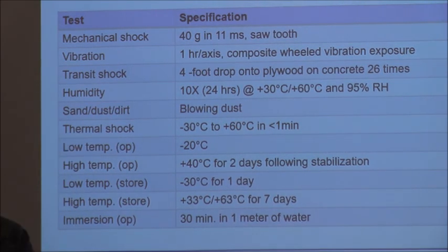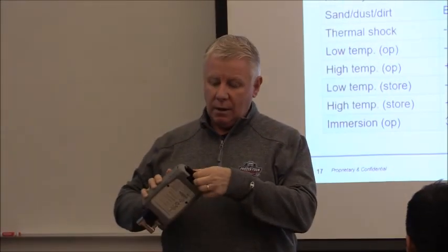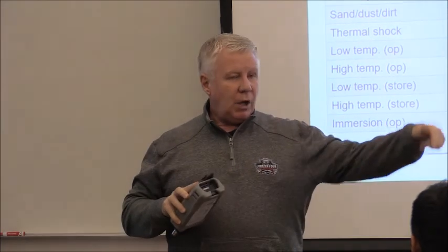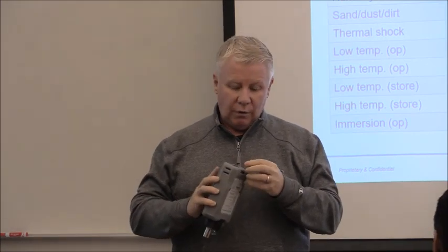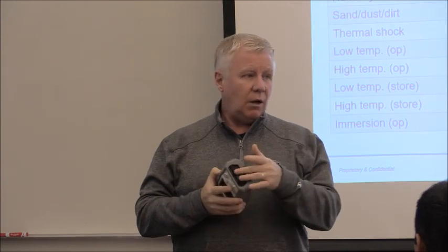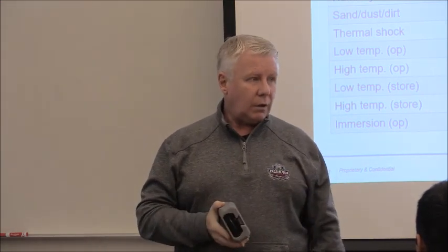As long as the bottom is closed and sealed. You have a bottom here, this just rotates, and this thing just picks it back up. It's attached by a little lanyard. The Gemini have the same thing, but on the sides. These don't come off. Just close them, seal them. So if you ever want to do decon, power down your device, seal up your unit, and that way you can really spray them or hose them and thoroughly clean them.